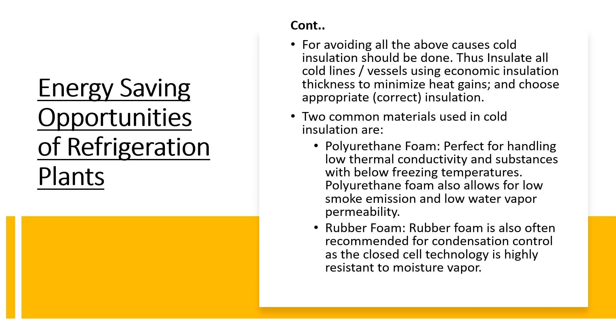Materials used for cold insulation include polyurethane foam, which is perfect for handling substances with below-freezing temperatures due to its low thermal conductivity, low smoke emission, and low water vapor permeability. Rubber foam is also often recommended for condensation control, as its closed-cell technology is highly resistant to moisture vapor.